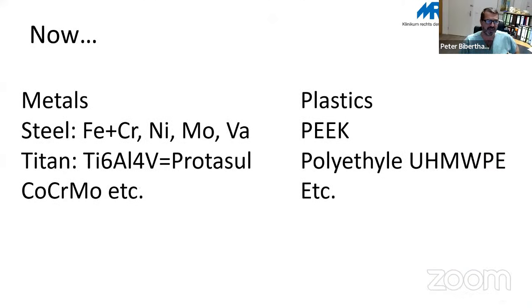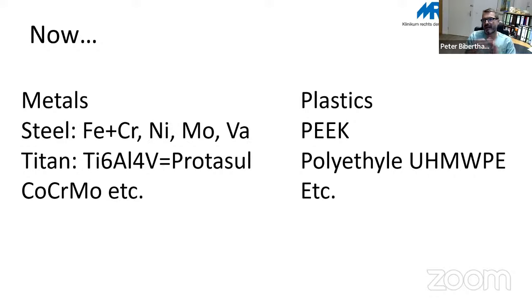Nowadays we have plenty of materials: a lot of metals, all kinds of steel alloys with chrome, nickel, molybdenum, and vanadium; several titanium alloys — the strongest being titanium 6 aluminium 4 vanadium, called Protasul; cobalt chrome alloys and a lot more. This is now a lot of metallurgical knowledge. We also have a lot of plastics: PEEK, polyethylene, and polyurethane — a lot of plastics where we also have to be aware of what we are doing.